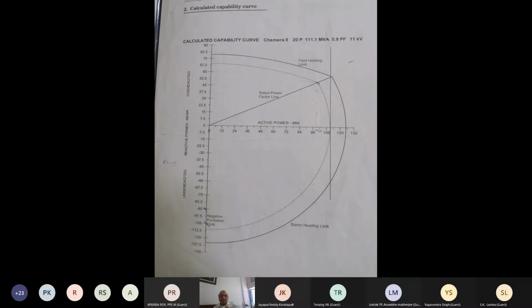It's not that the air gap flux requirement has come down, but the way air gap flux is managed is different in under-excited mode. Whereas in over-excitation mode, you are actually supplying reactive power, so the entire air gap flux is produced by the field current. That's why the field current value will be high. Because you are not drawing any excitation from the grid, you are supplying reactive power to the grid. So in under excitation mode, stator heating limit means stator core heating limit, no, sir? Yes. In under excitation mode, the heating limitation comes first. In over excitation mode, the excitation winding heating becomes the limitation.